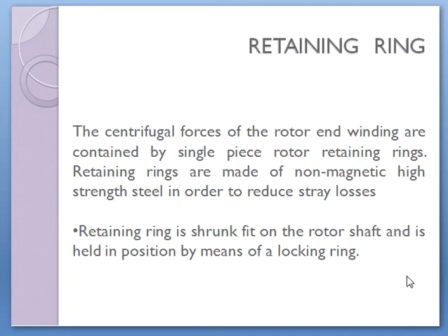These retaining rings are first heated so that they will expand a little, and then they are inserted on the end of the rotor, and they are shrunk fit on the rotor shaft and held in position by means of a locking ring.